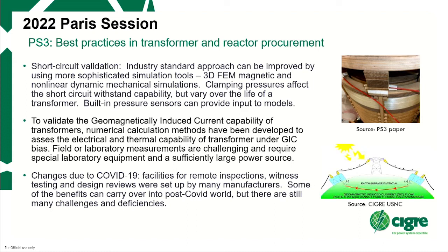But actually validating these in the field or in a test lab is turning out to be very challenging, as it requires special equipment and very large power sources. Depending on the size of the transformer, that could require connection to the system, which is a little impractical.